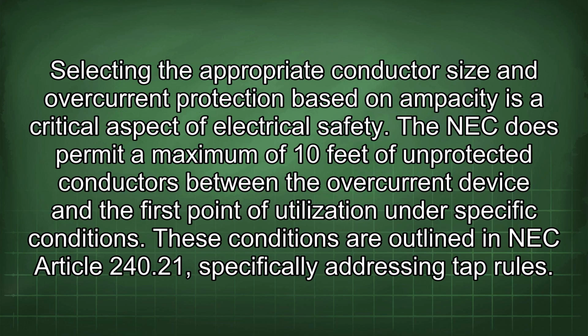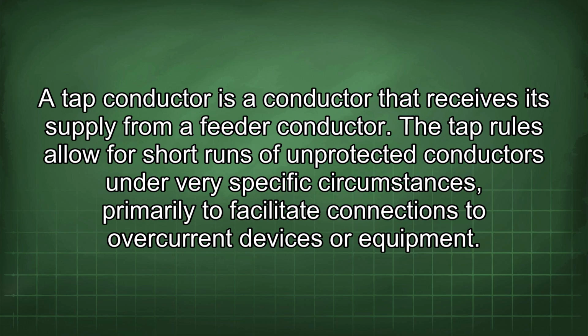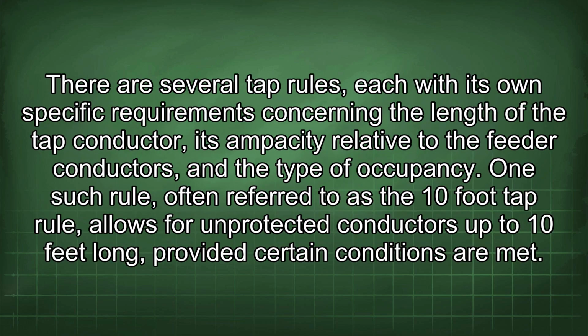safety. The NEC does permit a maximum of 10 feet of unprotected conductors between the overcurrent device and the first point of utilization under specific conditions. These conditions are outlined in NEC Article 240.21, specifically addressing tap rules. A tap conductor is a conductor that receives its supply from a feeder conductor. The tap rules allow for short runs of unprotected conductors under very specific circumstances, primarily to facilitate connections to overcurrent devices or equipment. There are several tap rules, each with its own specific requirements concerning the length of the tap conductor, its ampacity relative to the feeder conductors, and the type of occupancy.